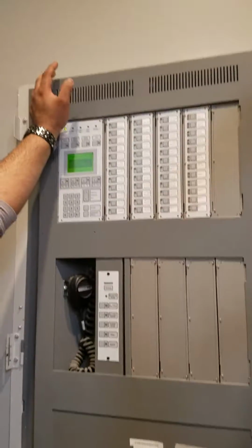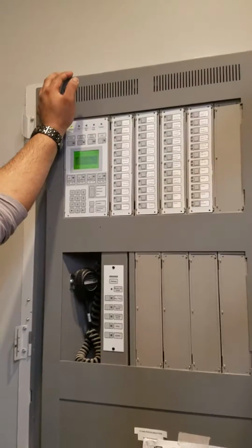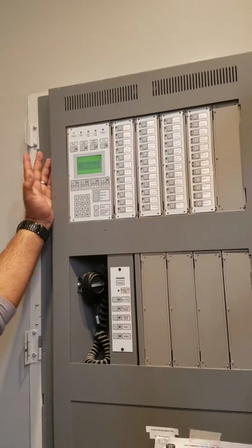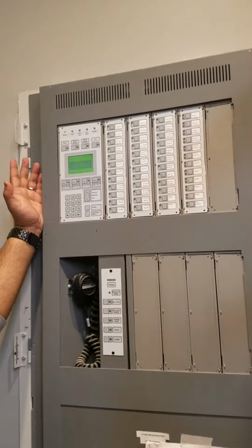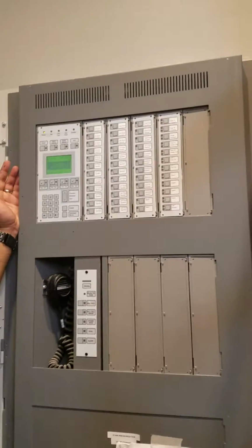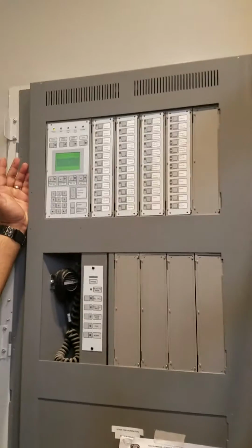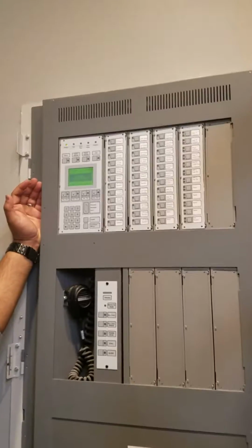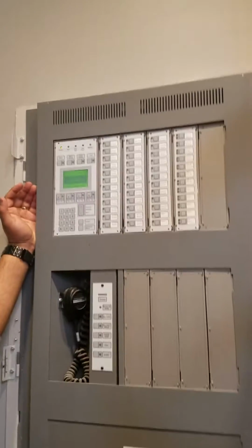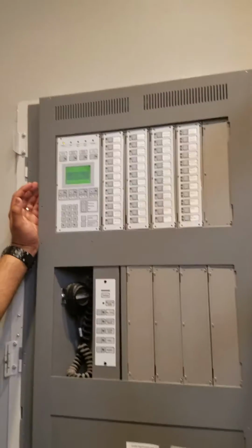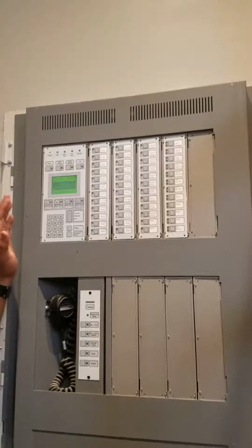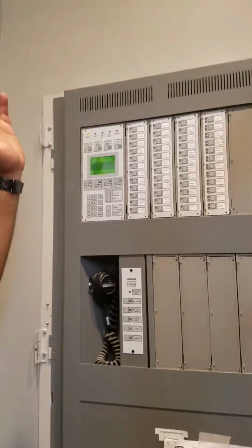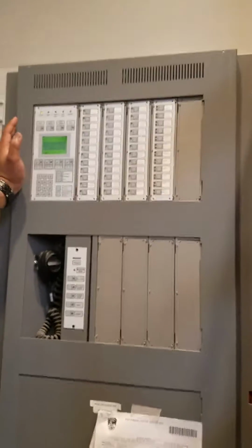Would bring your elevators down. So again, if you have a false alarm and it's coming from an elevator lobby, the first thing you want to do is actually come down to the panel and see where it's coming from. And go check before you reset. If it's dust in the air, if it's little smoke in the air, whatever, you take a booklet or a piece of paper, cardboard, whatever, fan it out, make sure nothing else is going on, and then you come and reset it. When you reset it, your elevator should just automatically kick back on.